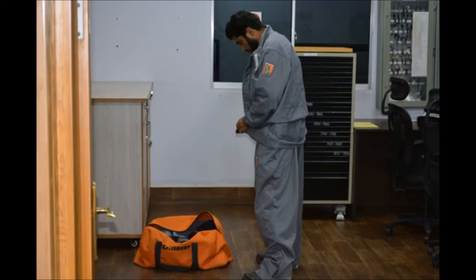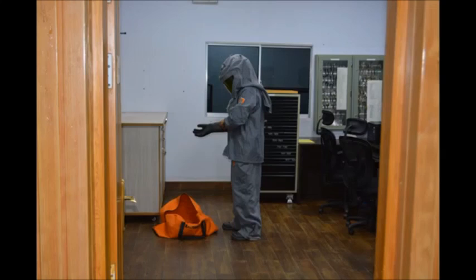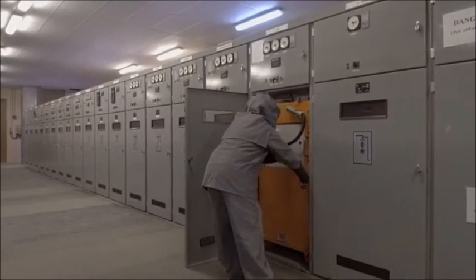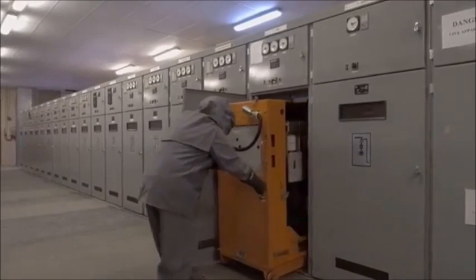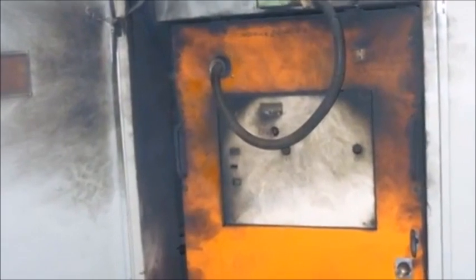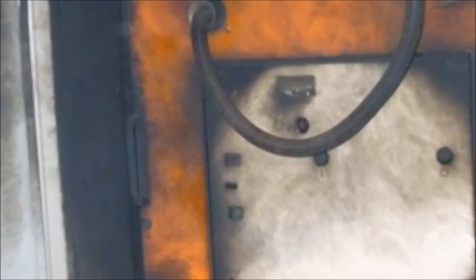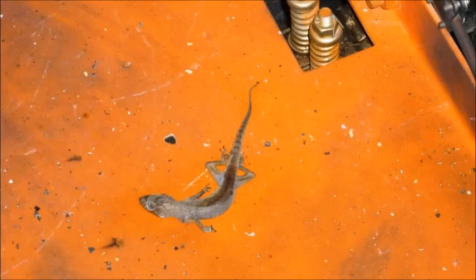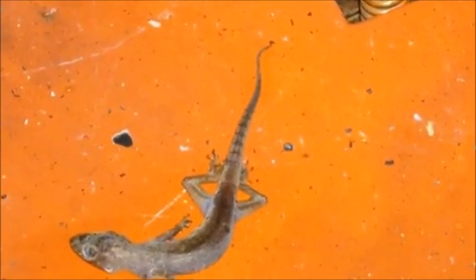After isolating the affected breaker, the shift charge engineer asked the control room operator to don the complete full body arc flash suit and open the breaker. The breaker was significantly blackened on external surfaces, including its breaker cubicle door. A dead lizard was found in the base of the breaker.